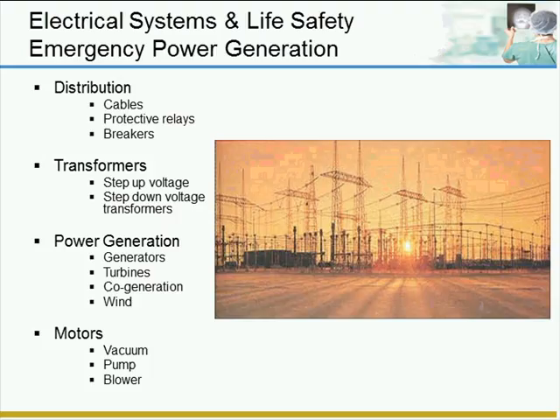The electrical system itself, electrical power distribution, is run by cables and wires and distribution bus. It's run in overhead trays and underground cable. The electrical distribution includes central power distribution circuits, branch circuits, small transformers, step-down units, typically 480 volt down to 208 or 120, and smaller localized distribution panels.